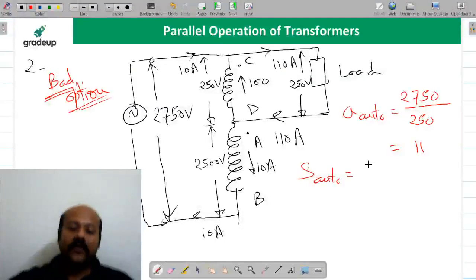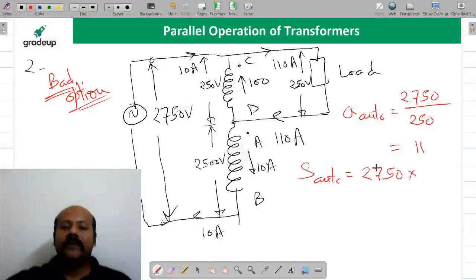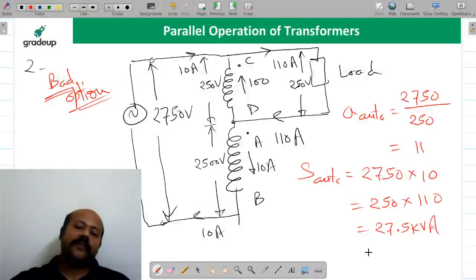The kVA rating of the autotransformer can be found either from the high voltage side or low voltage side. High voltage side: 2750 multiplied by current, which is 10 ampere. Low voltage side: voltage is 250, current is 110. You get the same value, that is 27.5 kVA. I hope you are getting this.